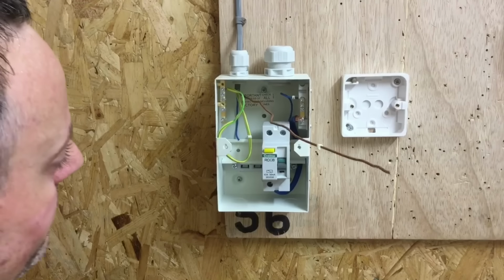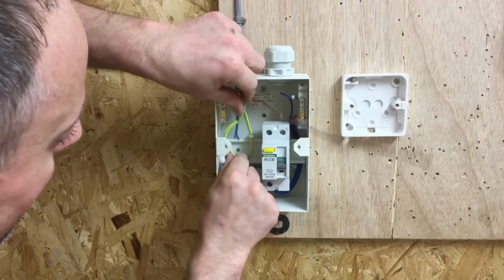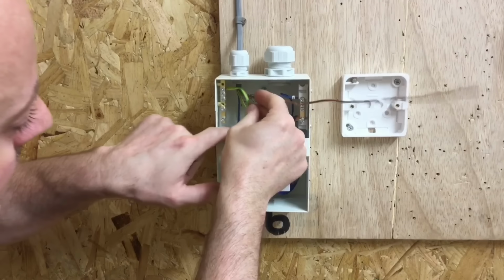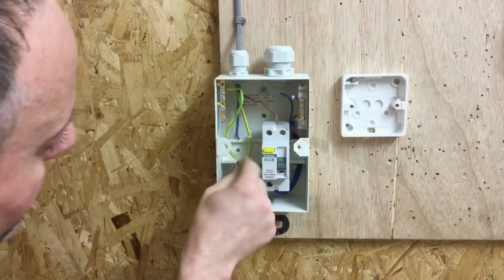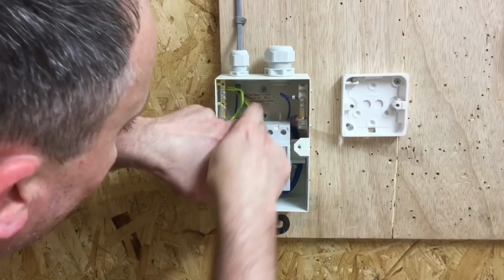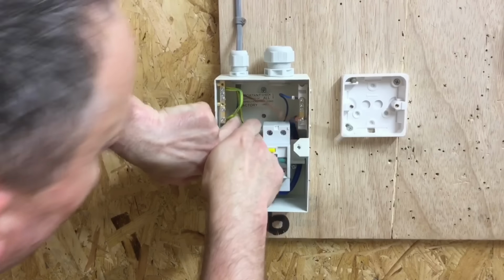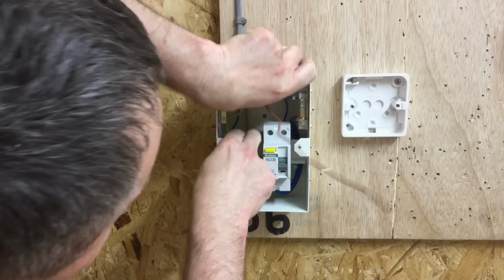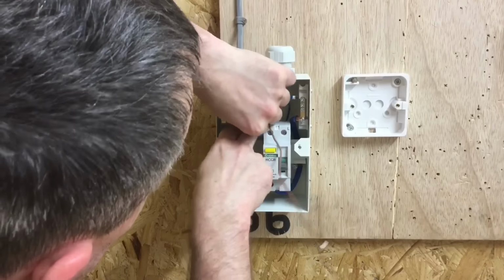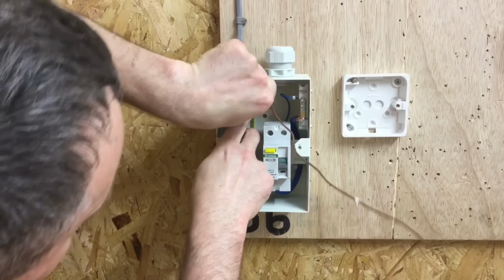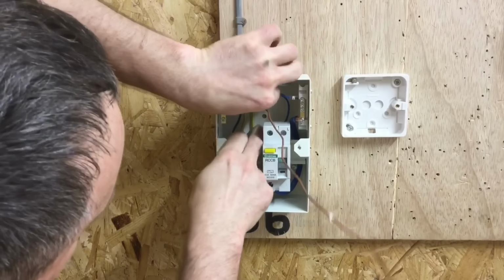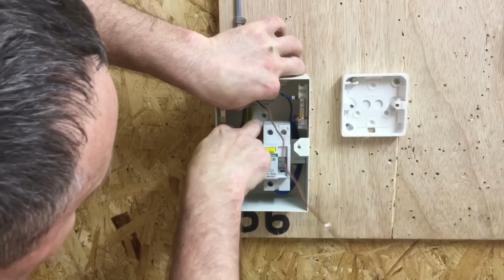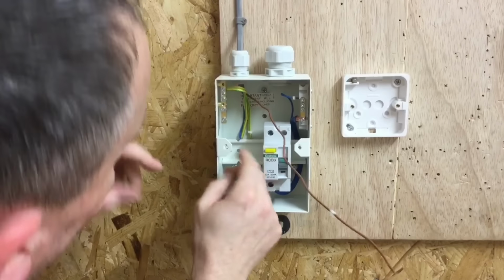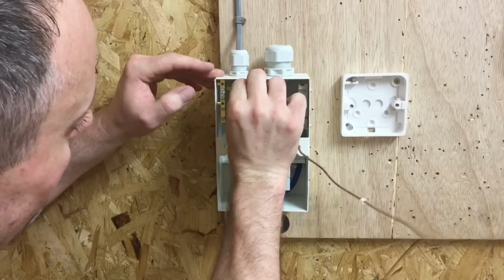And work to the correct torque setting, which is the same as the neutral bar at 1.7 Newton meters for this style of distribution board. So now I'm just going to pop the CPC back into a similar position to where the neutral was. Just use my fingers just to dress it back a little bit, and then back up again, and then put a nice smooth bend in it. It's going to take a little while to fiddle around and get them straight in there. So we'll go with that at the moment.